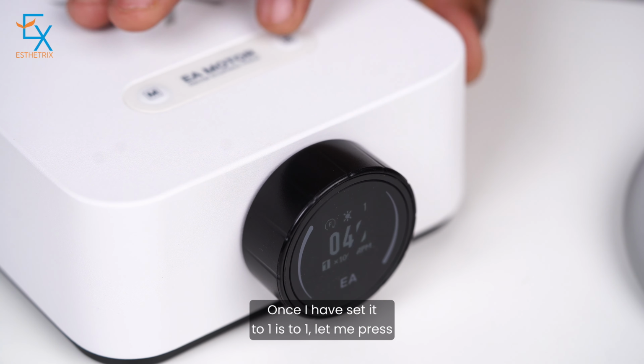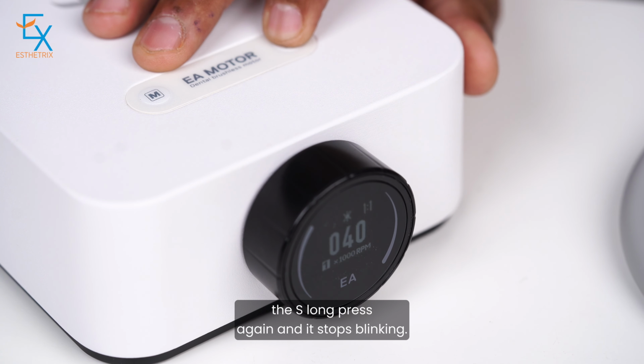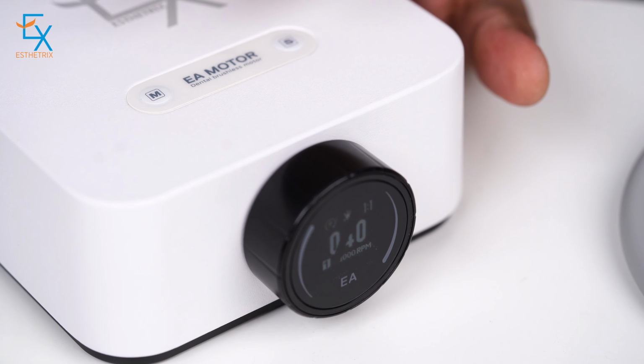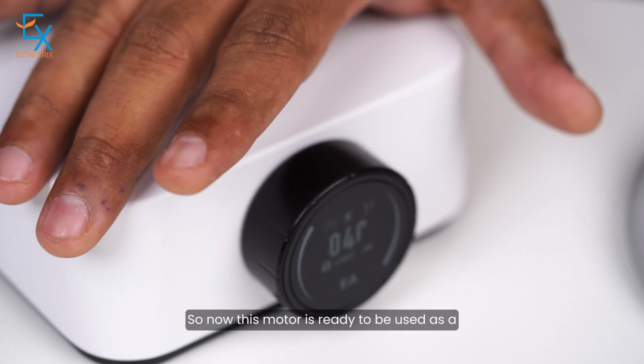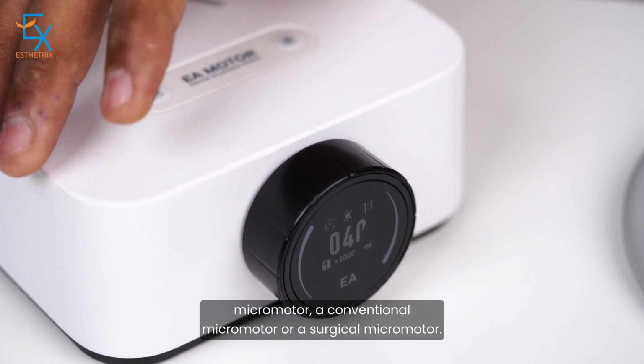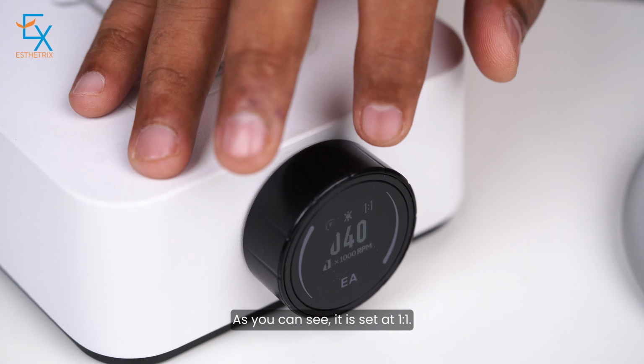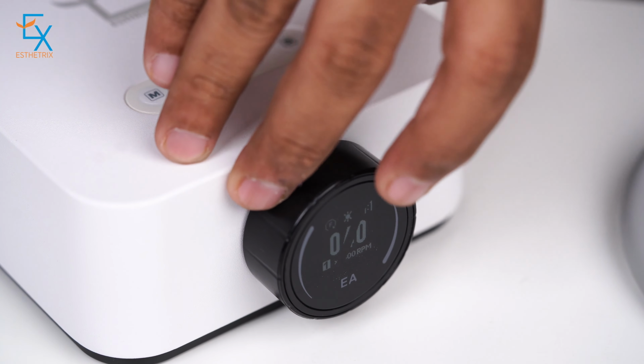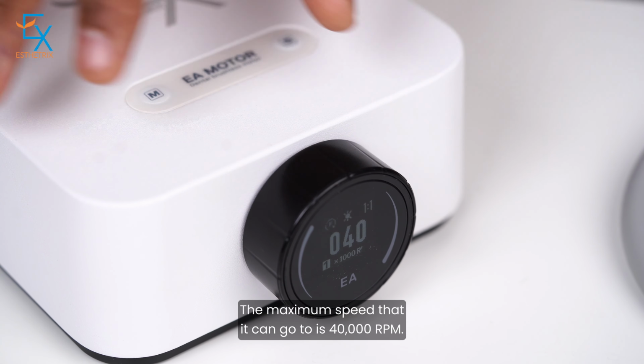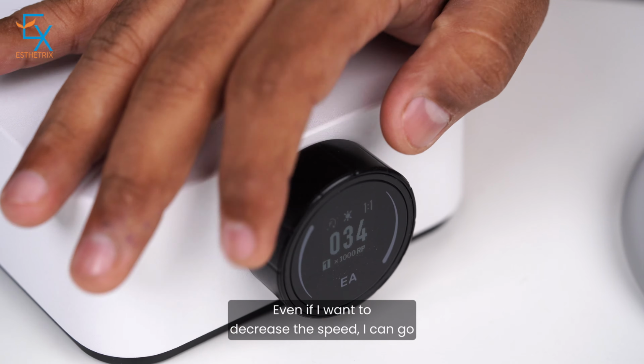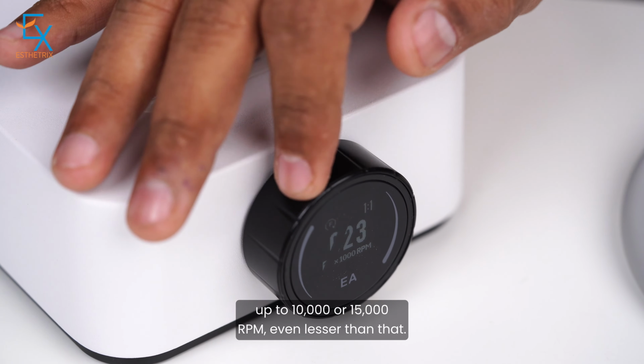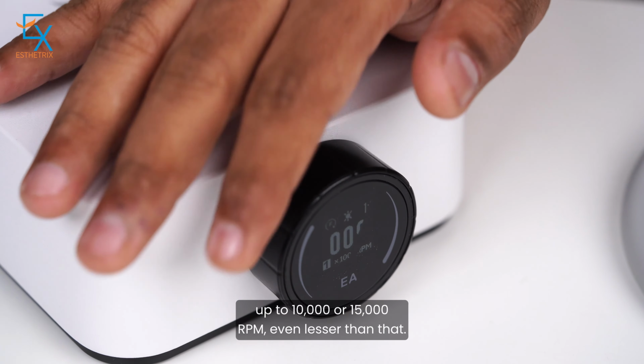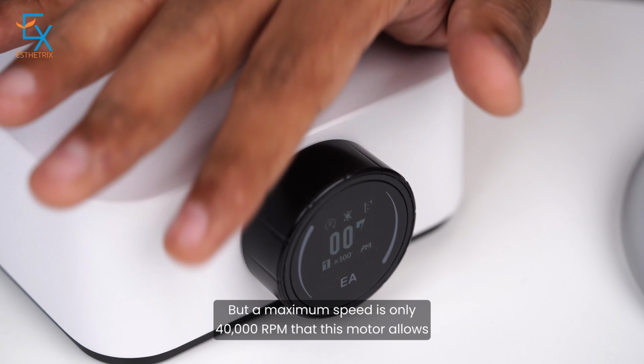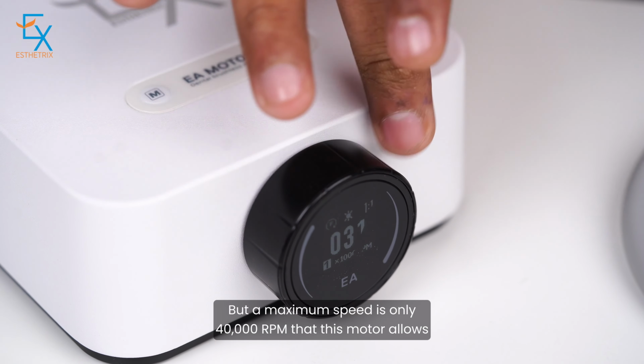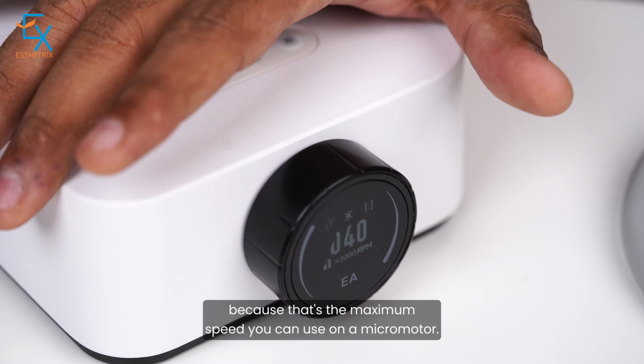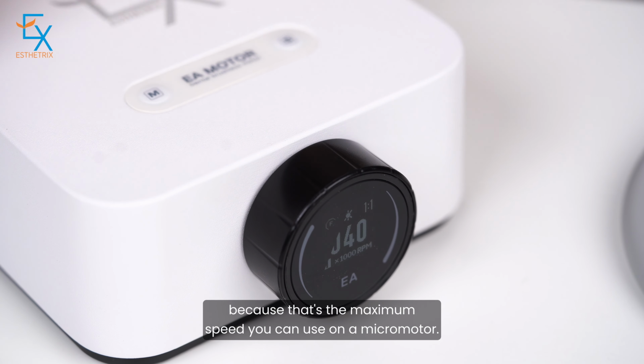Once set to 1:1, let me long press the S button again, and it stops blinking. So now this motor is ready to be used as a micro motor, a conventional micro motor or a surgical micro motor, set at 1:1. The maximum speed it can go to is 40,000 RPM. Even if I want to decrease the speed, I can go down to 10,000 or 15,000 RPM, even lesser, but the maximum speed is only 40,000 RPM since that's the maximum allowed on a micro motor.